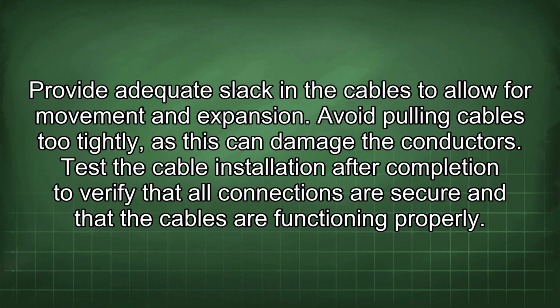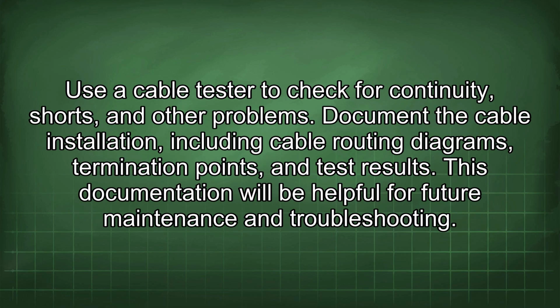Test the cable installation after completion to verify that all connections are secure and that the cables are functioning properly. Use a cable tester to check for continuity, shorts, and other problems. Document the cable installation, including cable routing diagrams, termination points, and test results. This documentation will be helpful for future maintenance and troubleshooting.